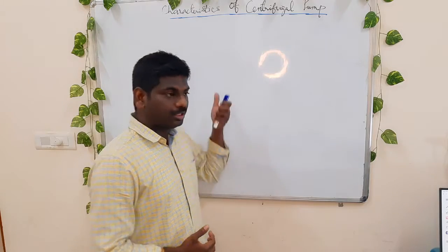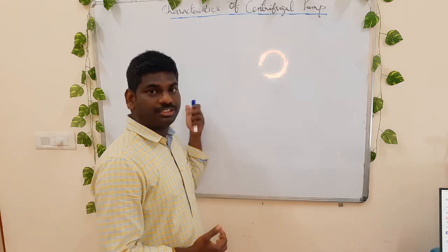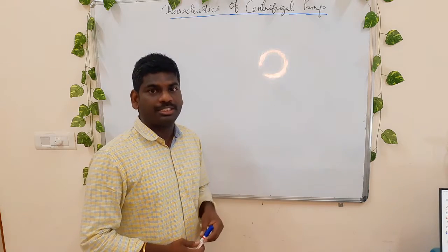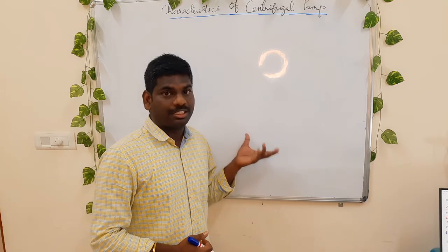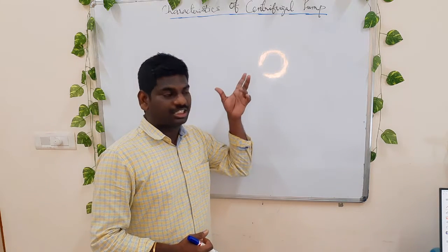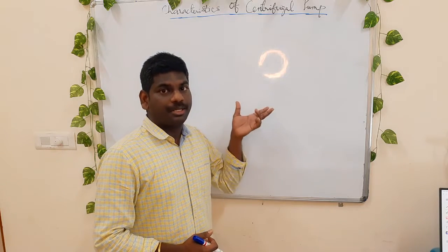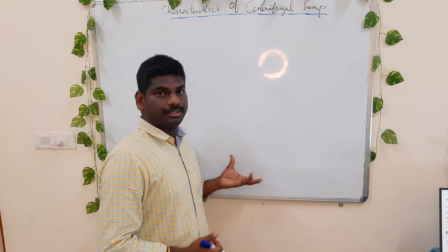That is what we see, the characteristics like discharge versus head, discharge versus efficiency, and discharge versus the input power. Based on this plot, we try to see the optimal level for the particular discharge. What is the optimum efficiency, right? Based on the efficiency, we see what is the discharge and the input power required. That will be drawn from this characteristic of the centrifugal pump.